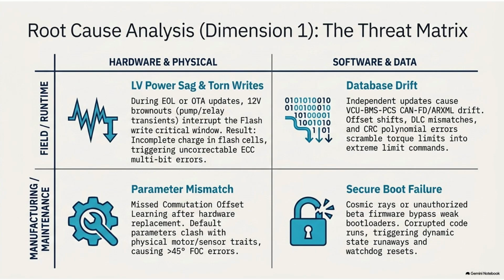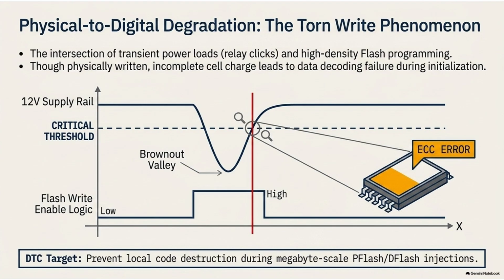Unconstrained current, meaning way more electricity than the physical wires are designed to handle. It is a massive thermal spike. Inside the motor controller, the power is handled by advanced microchips called silicon carbide, or SiC power modules. They're designed to handle hundreds of amps of current efficiently, but they're still physical materials. When that direct axis overcurrent hits them because of a 45-degree software timing error, the thermal shock destroys the silicon carbide in milliseconds. They literally blow up.